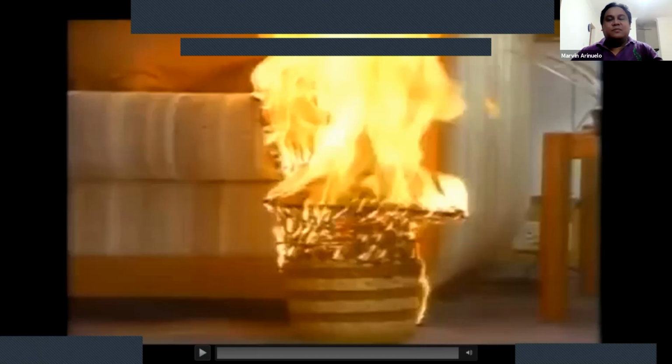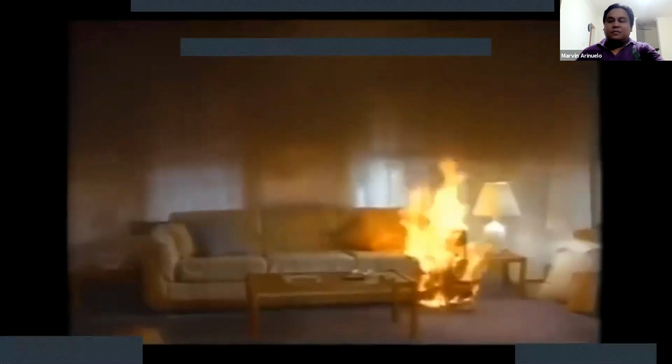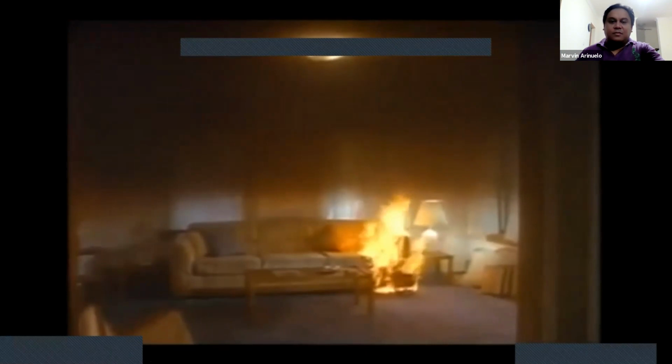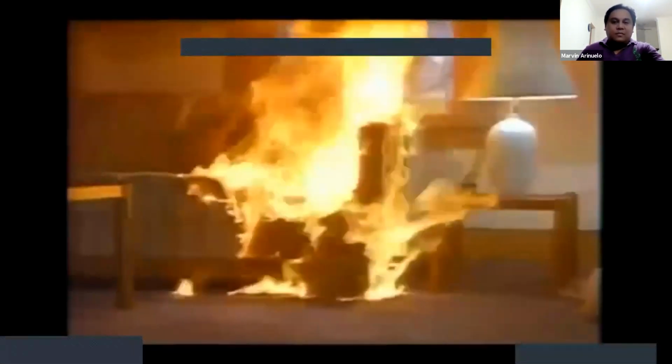1 minute 4 seconds from first flame. Smoke begins to fill the room. 1 minute 35 seconds. The smoke layer in the living room descends rapidly. Gases flowing out of this room now exceed 190 degrees Fahrenheit. 1 minute 50 seconds. The smoke detector at the foot of the stairs sounds an alarm, providing warning before exits are blocked. Take action immediately. Crawl low where the air is cleaner.